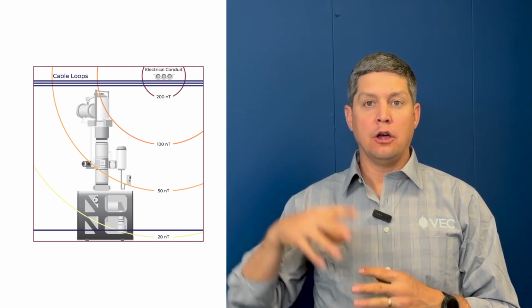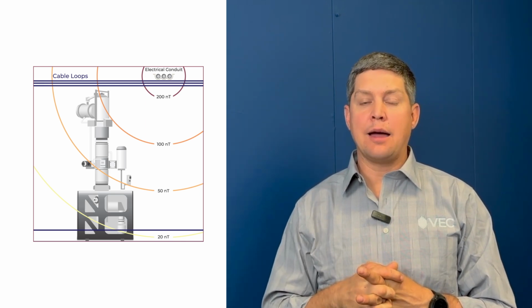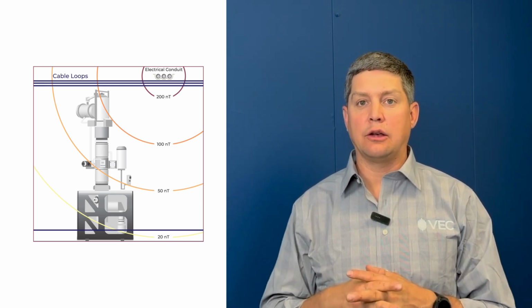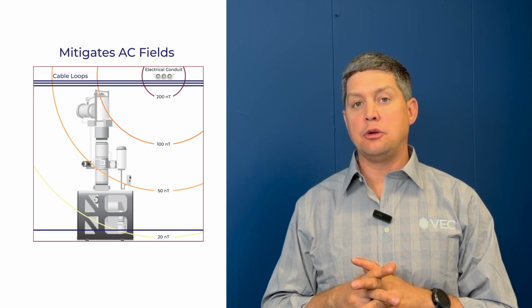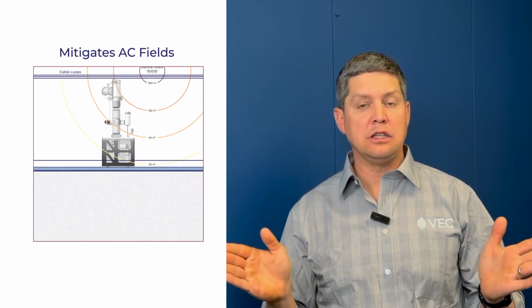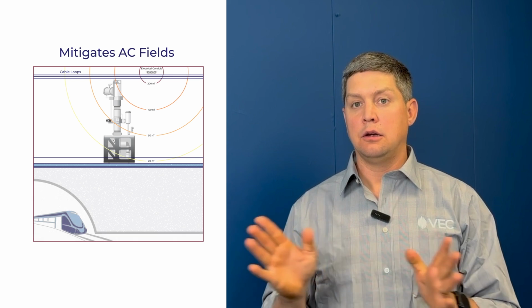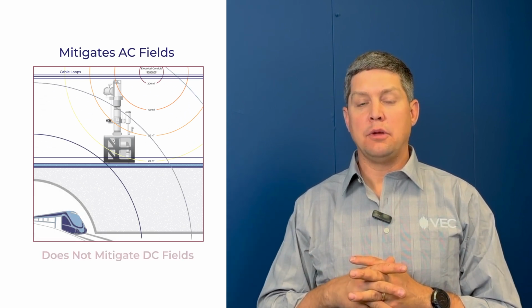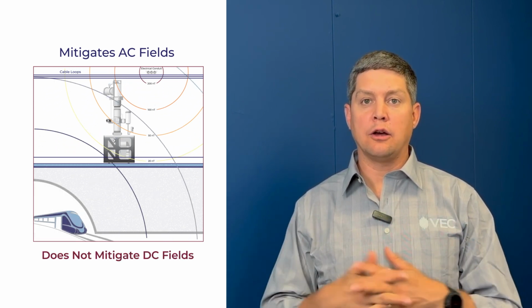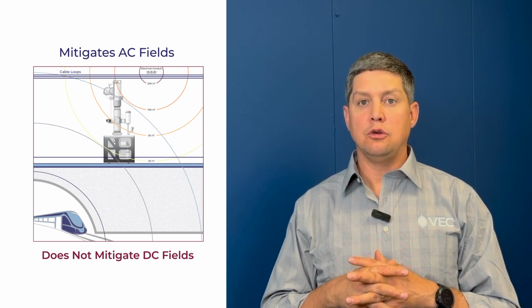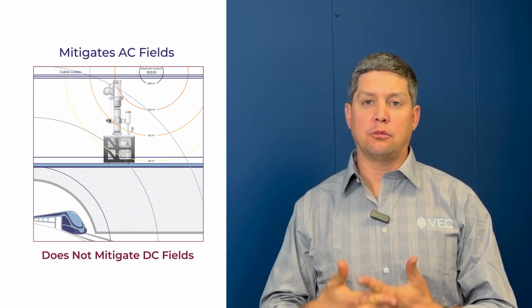So imagine you have electrical conduits above your lab, and you're persistently handling that field gradient, but then you have an intermittent source of, say, DC fields coming from a train below your lab. Because the field gradient is hardwired into the system, you cannot handle the different gradients from different directions. And so although you'll be fine mitigating the consistent AC fields from the electrical conduit overhead, you will not be able to handle the field gradients from the DC fields coming from the train underneath.